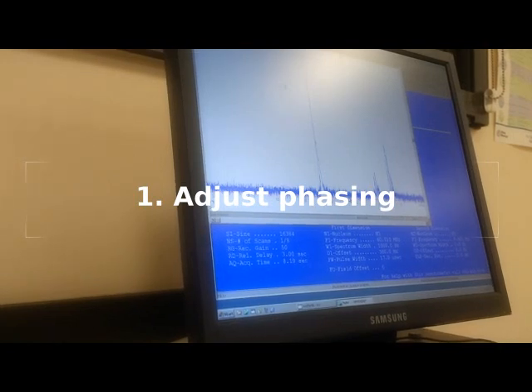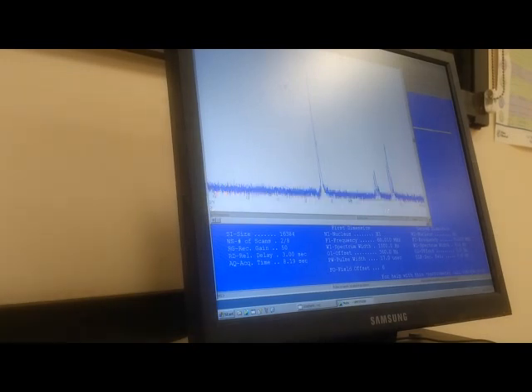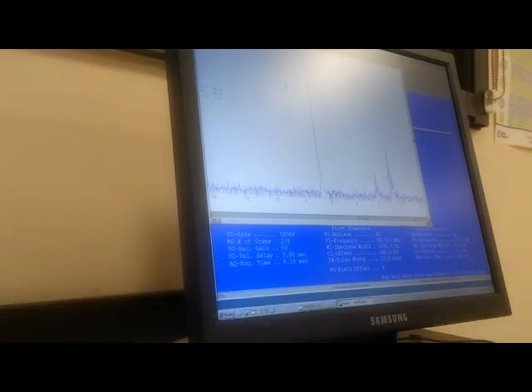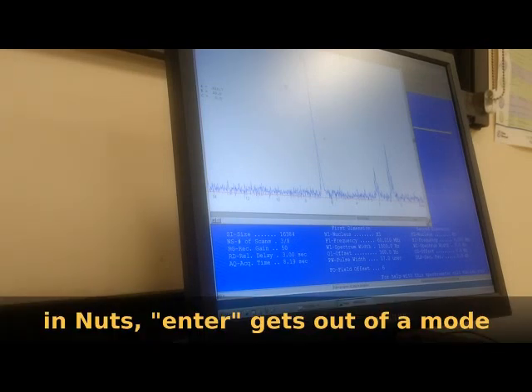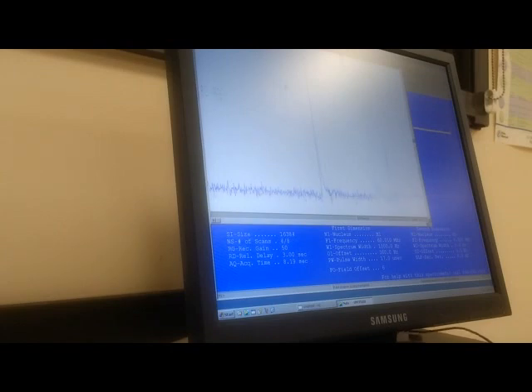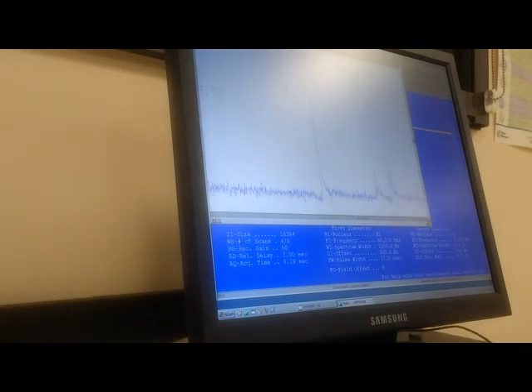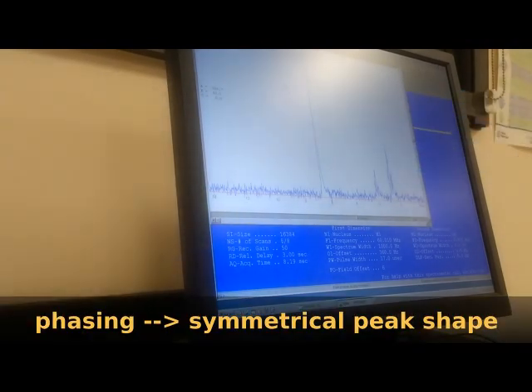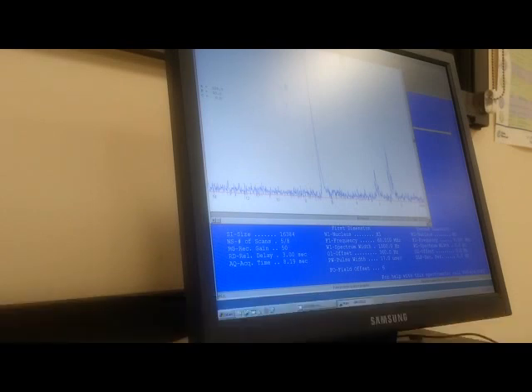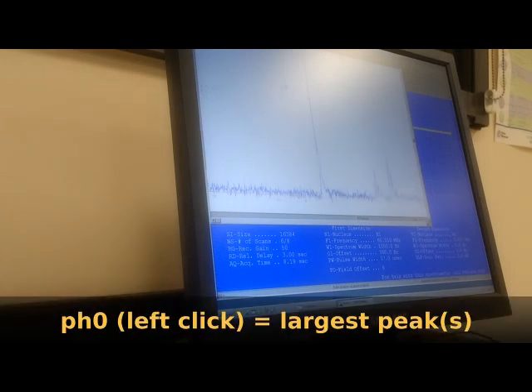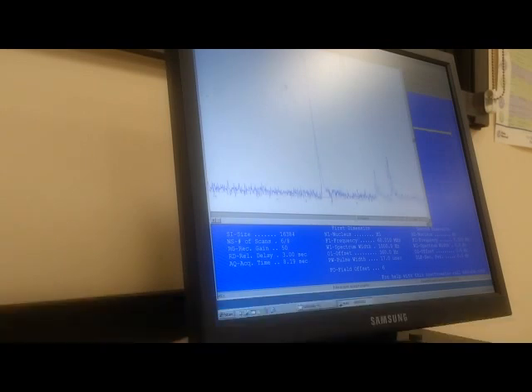Now to process the NMR spectrum using NMRNuts, the first thing you want to do is to adjust the phase or phasing. And to get into the phasing mode, you want to type pH. You don't have to hit enter. In fact, if you hit enter, you get out of the pH or phasing mode. And once you're in this phasing mode, you want to use your mouse, either the left or right mouse click and drag. And I don't know if you can see what's happening. I'm dragging the left mouse button and I'm adjusting the overall phase. Now phasing has to do with sort of how straight or how symmetrical each peak in NMR spectrum looks like. And you want to adjust that until everything looks as symmetrical as possible. First you want to do the left mouse click and then you want to do the right to adjust some of the other peaks. And once you have a nice symmetrical NMR peaks, you want to hit enter to get out of the phasing mode.